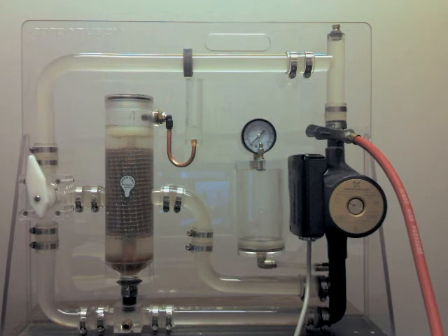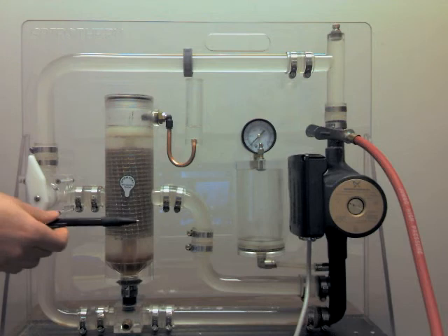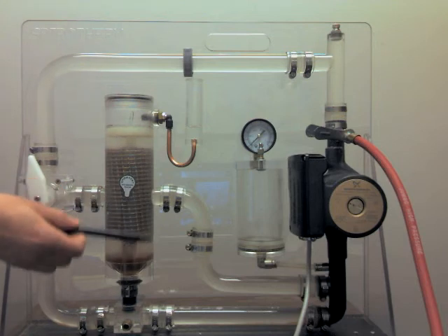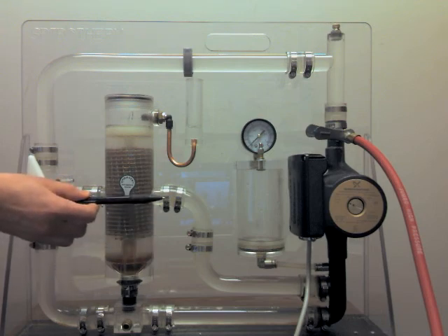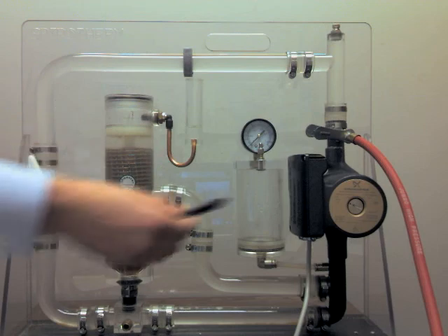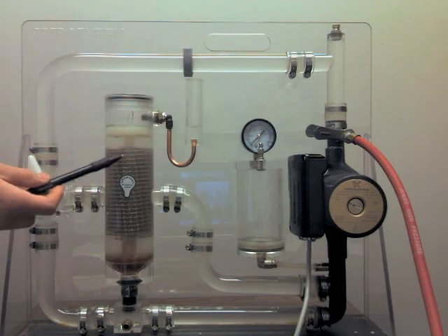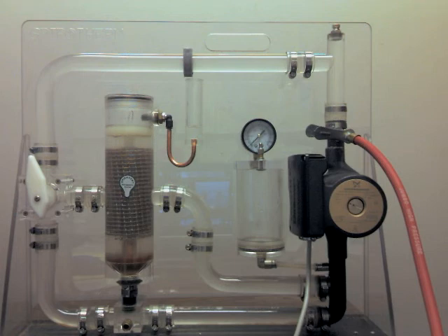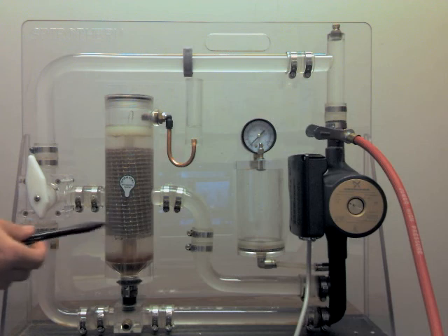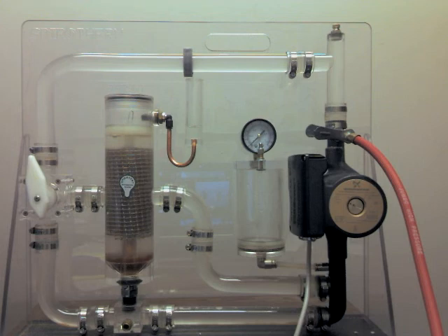Now, we get asked a lot, do these things clog? And the answer is no. The mesh is designed not to clog, and so is the way the vessel is constructed. As it's pulling debris, it can only rise up to the bottom of the pipe. And then it's just going to continue to circulate whatever material is left in there. It'll still remove air, it just loses its ability for any dirt particles to fall until somebody is able to purge the vessel. We've seen them go for months at a time where there's been a bunch of crud in there, and the system pressure just flushes it right out.